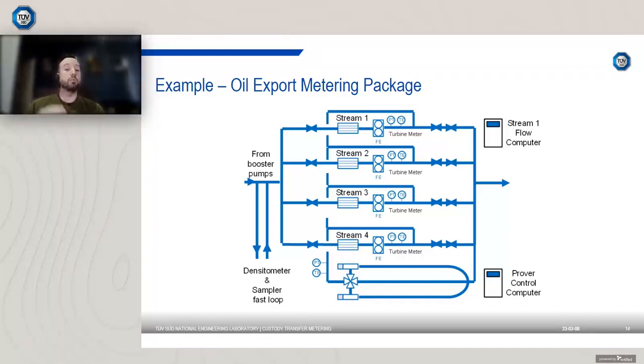There's a prover loop, which you can periodically use to verify the performance of the turbine meters and determine things like meter factors. Each stream has a flow computer, or there might be one flow computer for all the streams, and that will be collecting things like the pulse train from the flow meter and the raw temperatures and pressures. It might take in composition measurement from your gas chromatograph and values from your densitometer, and ultimately will produce things like gross standard volume for you. And there's also a densitometer and a sampling fast loop, where you can quickly take a sample from your flow stream.